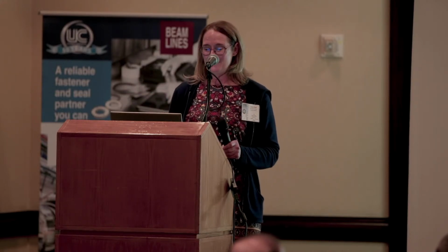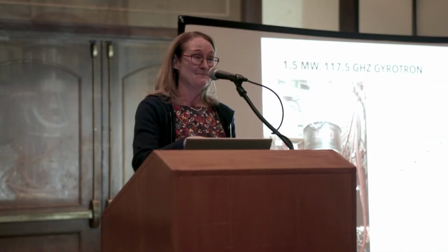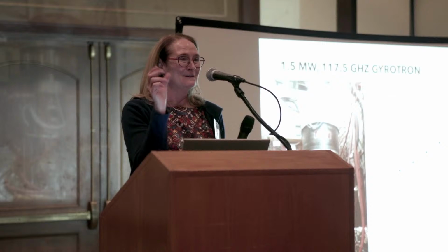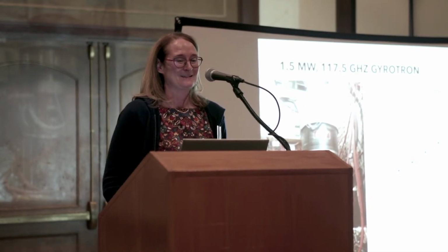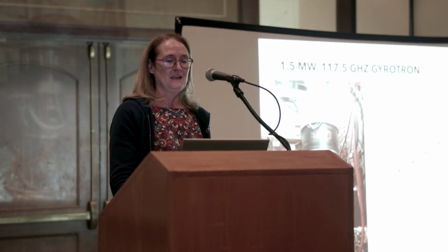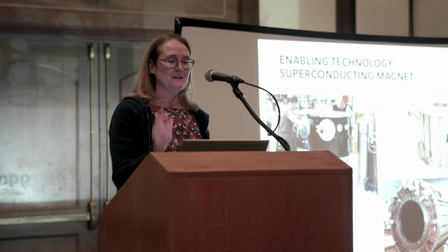On the flip side, a superconducting magnet like the one here runs off 208 single phase, 20 amps. It runs at 40 amp power supplies that operate at 1 volt because that magnet's superconducting, so you just need to overcome the external connections, sort of. That's a huge change, and I'd call it an enabling technology.